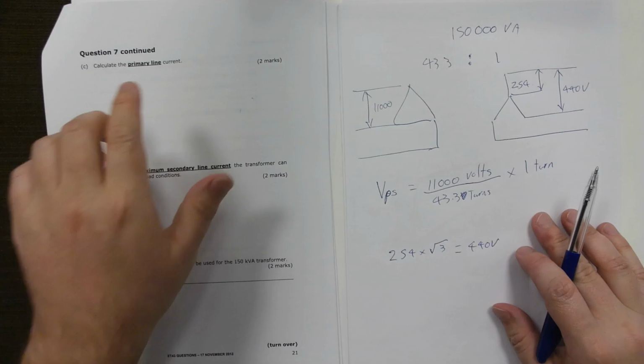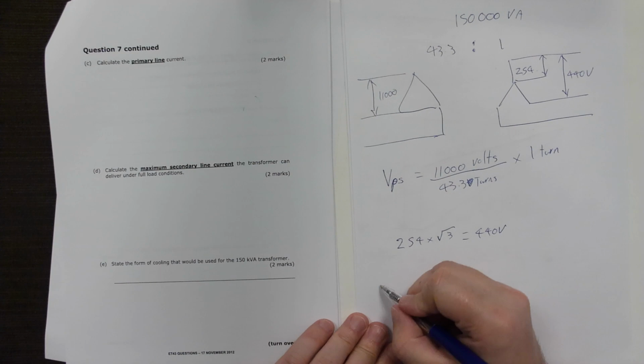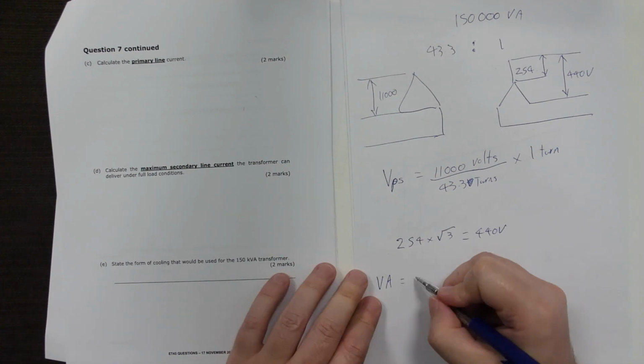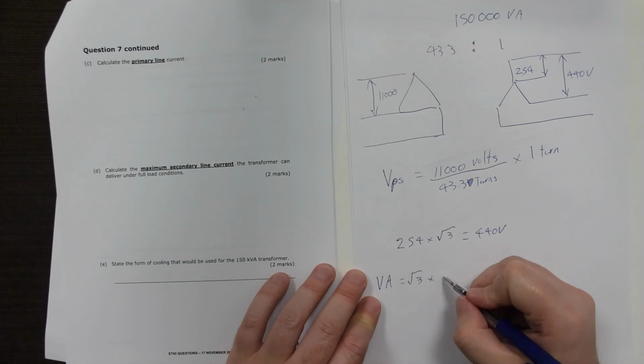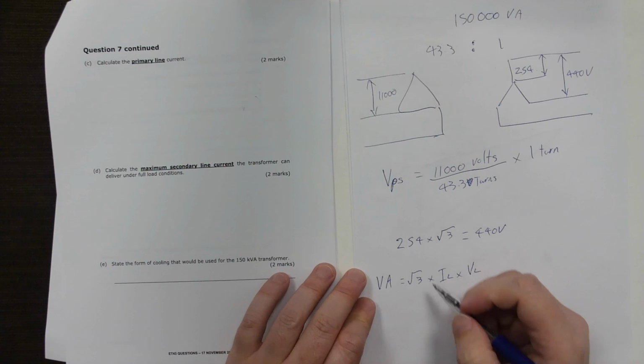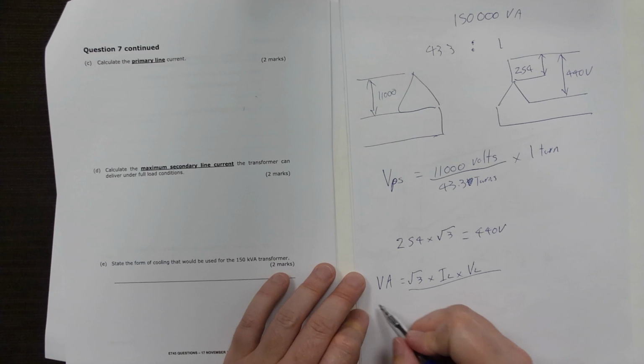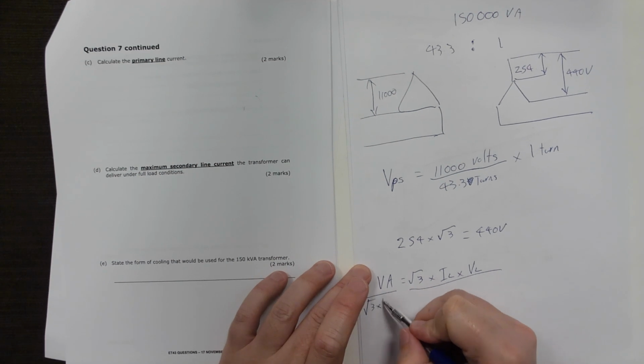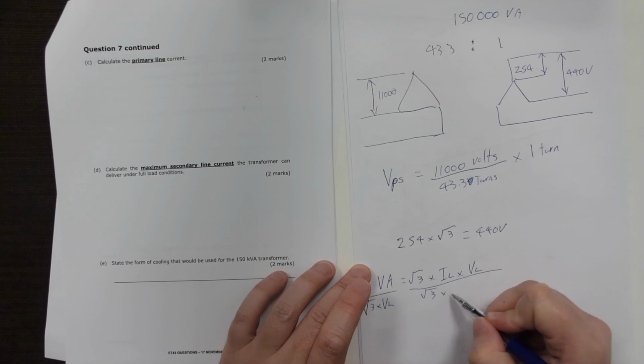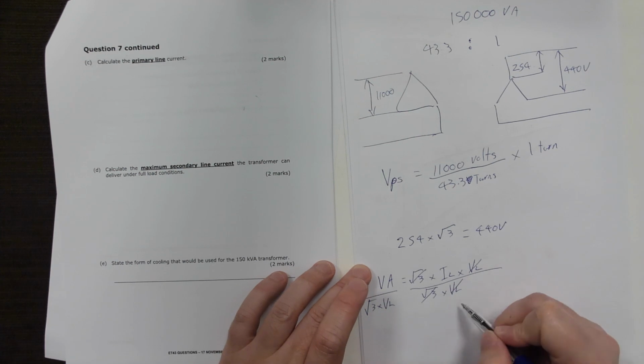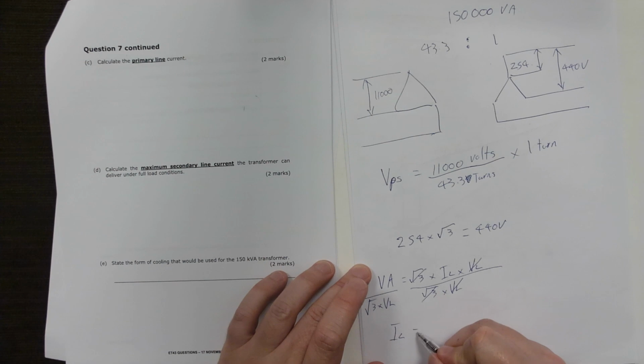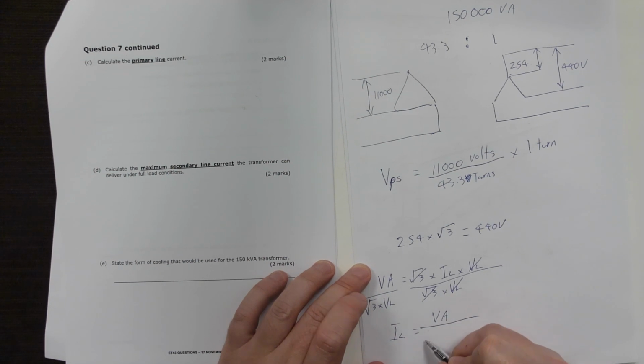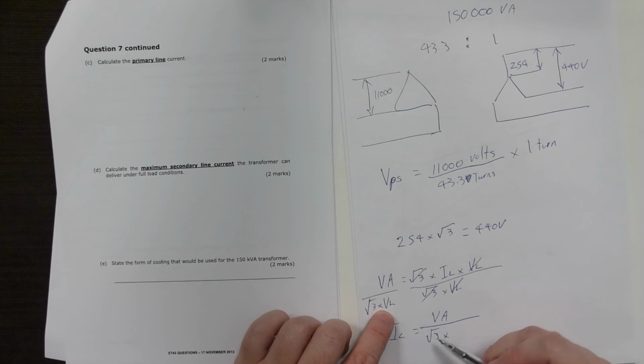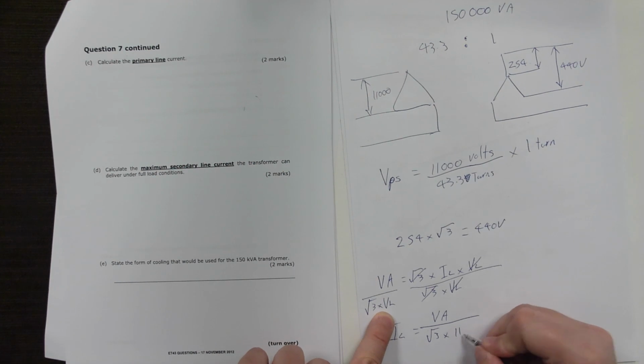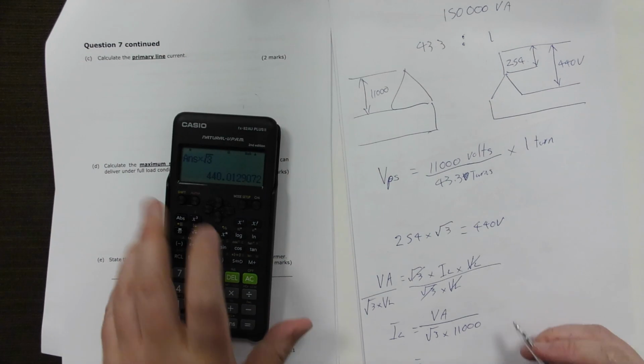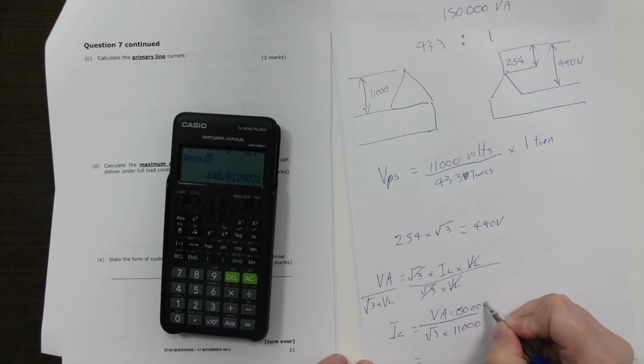We come over thereafter to the primary line current. For this one, we go VA equals, and because this is 3-phase, root 3 times I line times V line. Now we want to rearrange this so that it's I line equals. So we divide both sides by root 3 times V line, and they cancel out. So I end up with I line equals VA over root 3 times V line, and because this is our primary line current, V line is 11,000. VA equals 150,000, standard across the whole transformer.